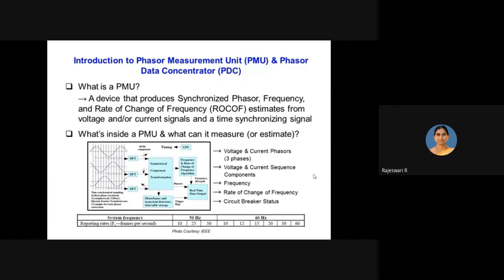So the processor is programmed to convert the sampled signal into phasor form, which is generated and conveyed. The processor is also provided with a program to calculate frequency and capture voltage and current sequence components, that is positive, negative, and zero sequence components. Once voltage and current phasors are all measured in phasor form, it is easy to convert them to sequence components, determine frequency, rate of change of frequency, and also the circuit breaker status with the help of the acquired voltage and current.